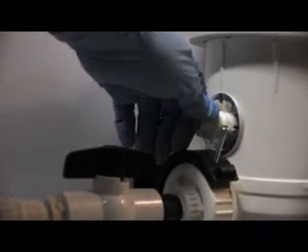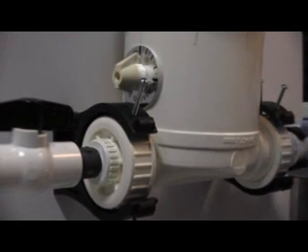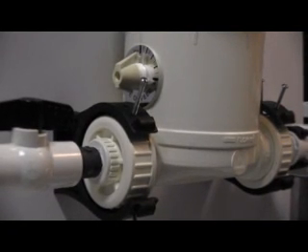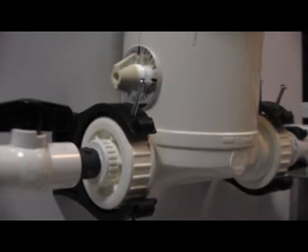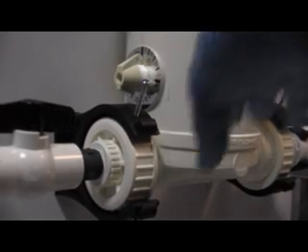But the reason I say that it's not completely off is there's a lot of residual coming through this system. And I'm describing residual as carryover from this point to the end point. So even though you put it on off, it could be a while before there's completely no chemical on this side. Okay? It's going to be a while. So I don't want you to think of that off as being off right away. Think of it as off over a period of time, and that period of time has to include the flushing of all possible residual chemistry that's caught in this chamber.